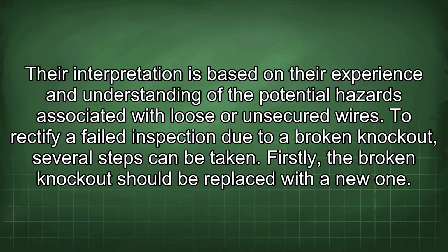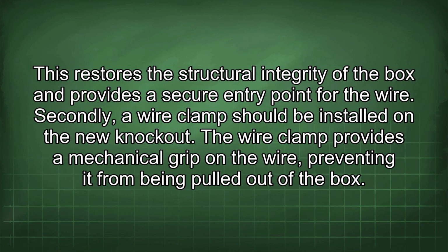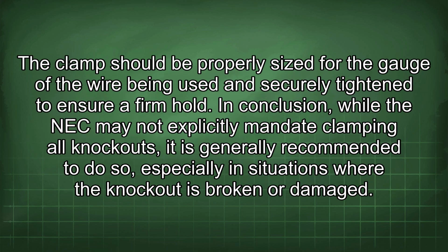To rectify a failed inspection due to a broken knockout, several steps can be taken. Firstly, the broken knockout should be replaced with a new one. This restores the structural integrity of the box and provides a secure entry point for the wire. Secondly, a wire clamp should be installed on the new knockout. The wire clamp provides a mechanical grip on the wire, preventing it from being pulled out of the box.